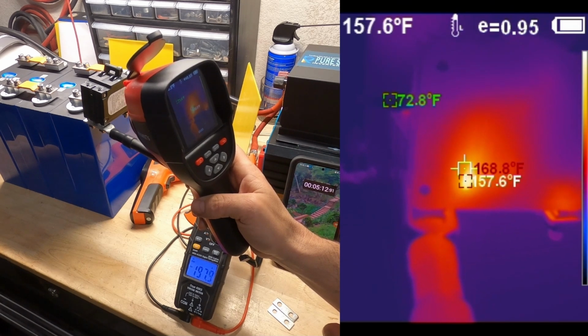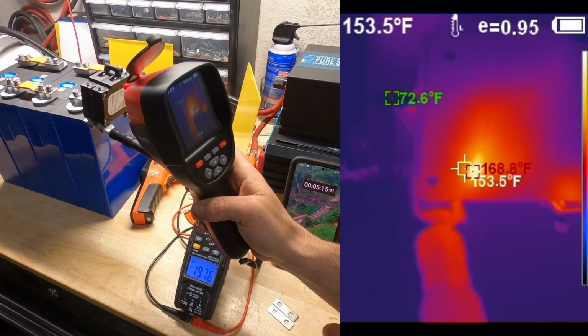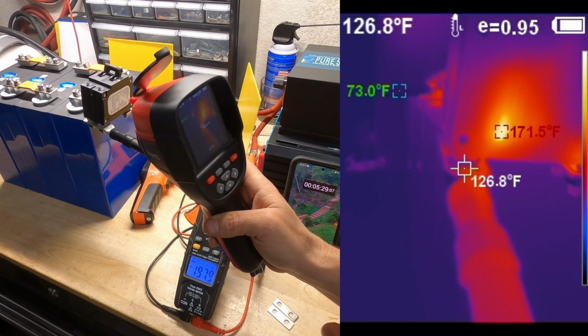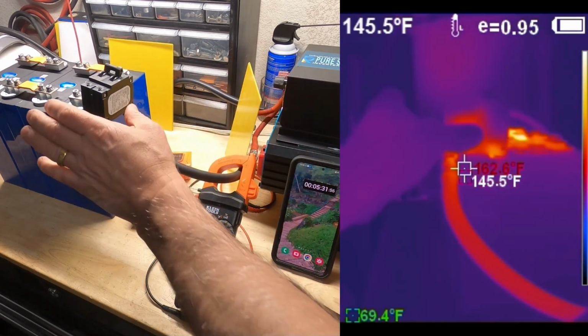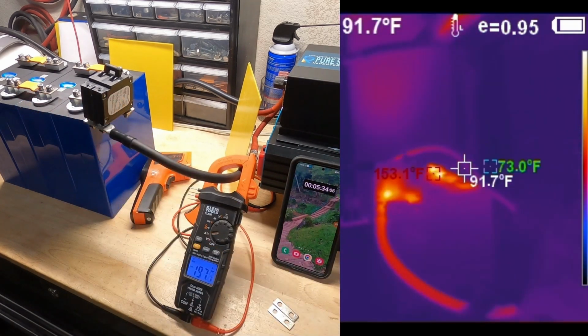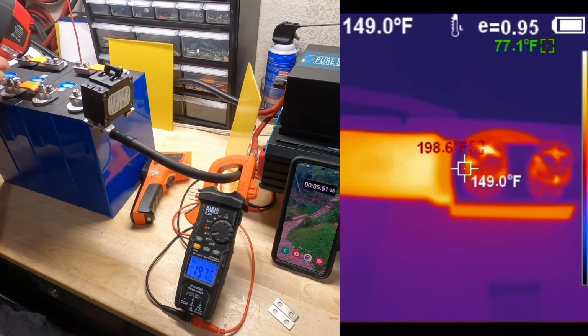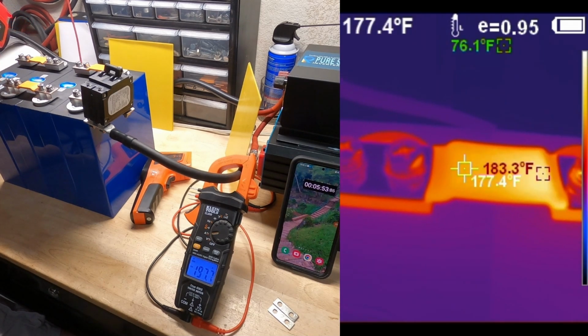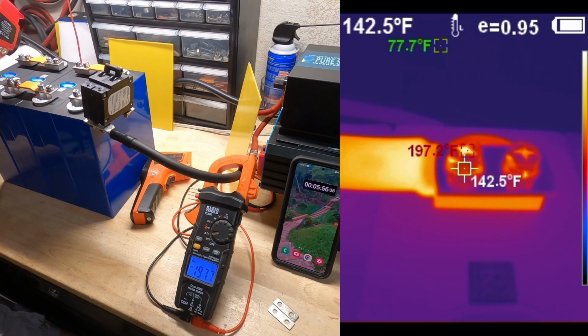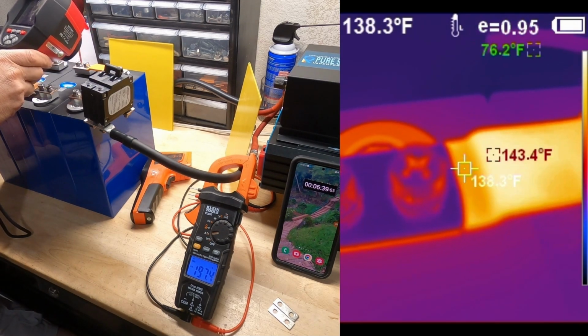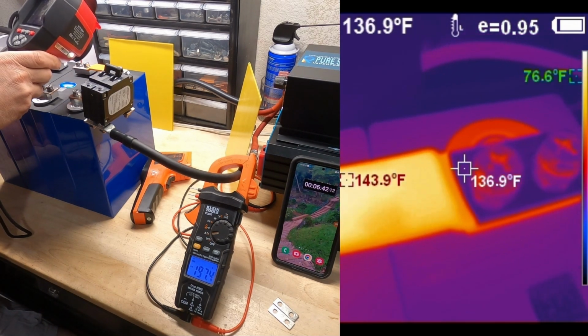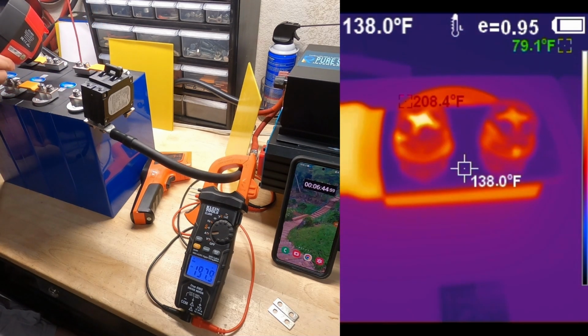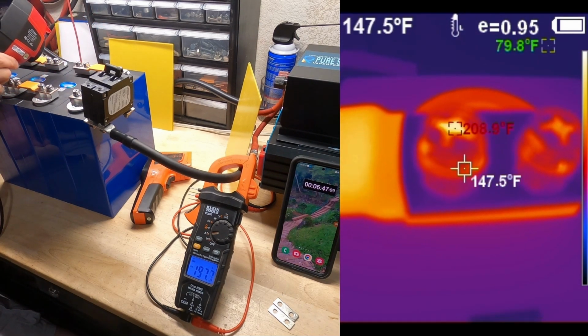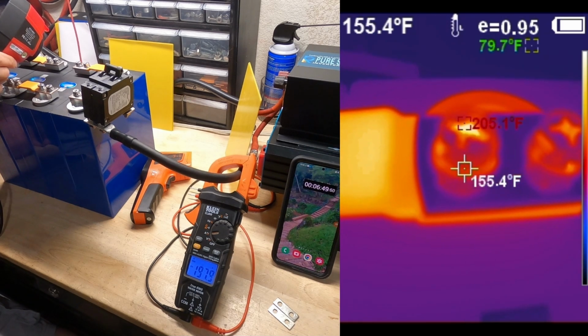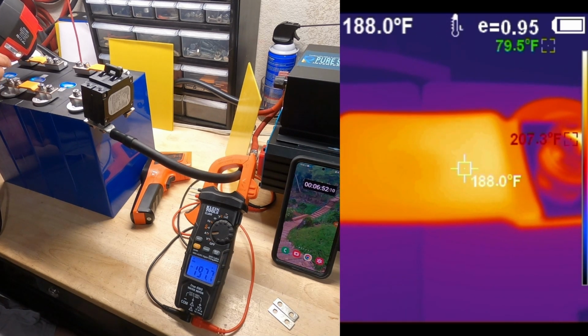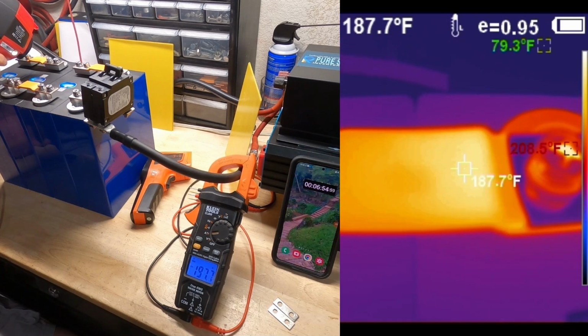The internals on the breaker itself. Wow, look at that internal temp. That is crazy. That is right here. Yeah, that's warm. Still pushing 200 degrees on that bus bar. Wow. Same there. That's consistent. That's 140 degrees on that one. But you go to this one and look at that. Wow. 160 on the target with a max of 202. What is up with that one?